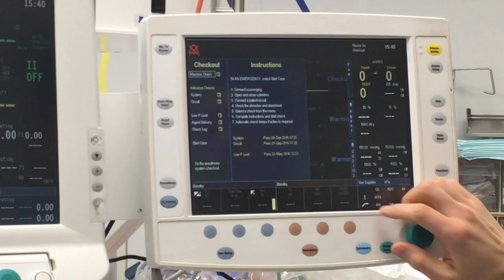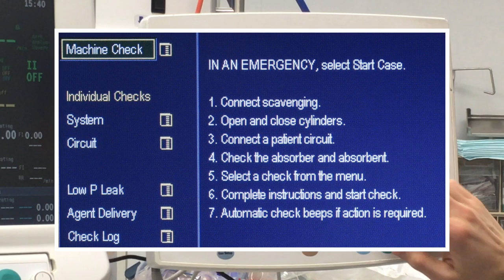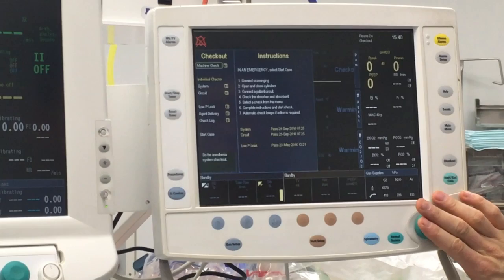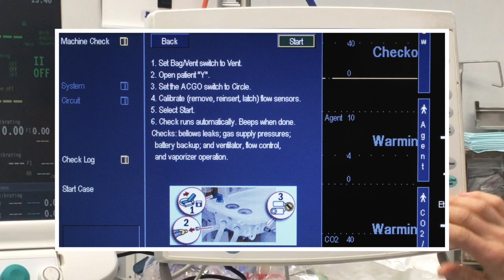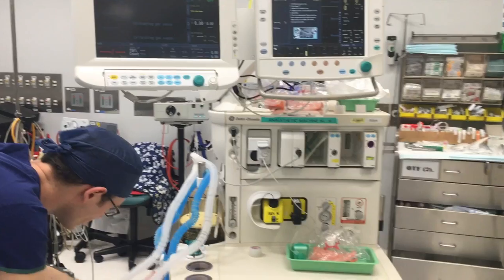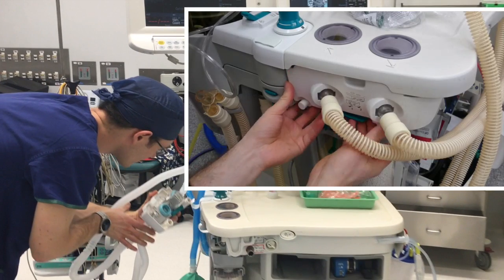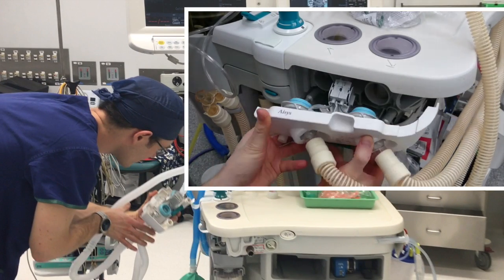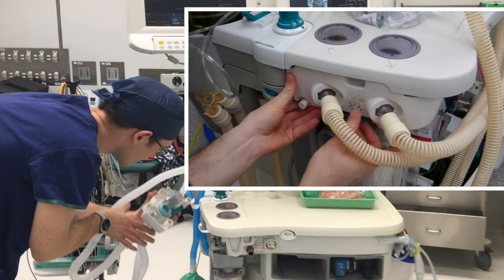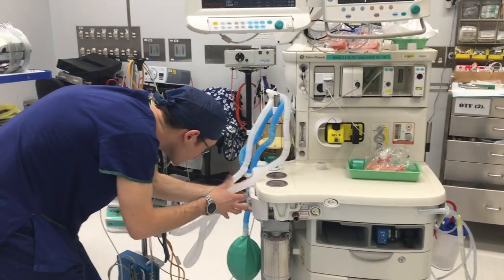The home screen has the machine check option already selected in the top left. All you need to do is push the main green button to bring up the next menu. The machine tells you a few things to do before selecting Start. Go around to the side of the machine and remove the flow sensors before putting them back in. This resets the sensors and zeroes them to atmospheric pressure.